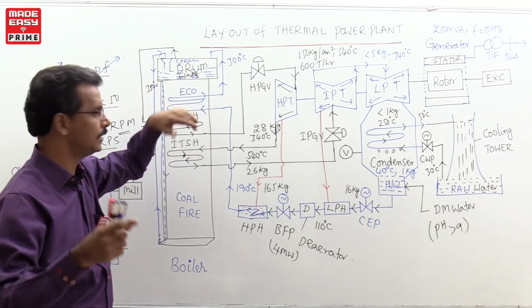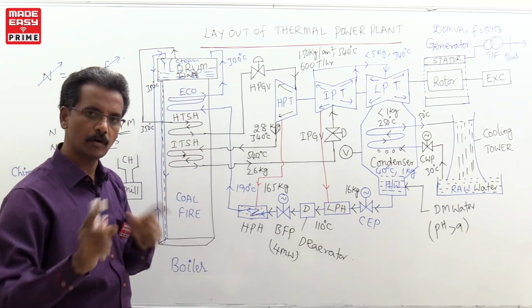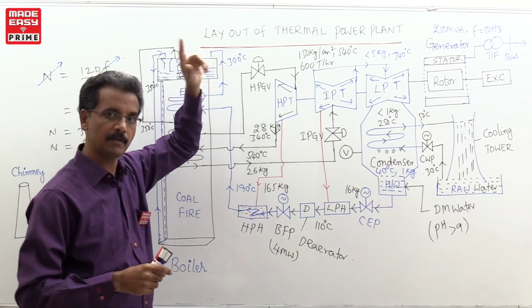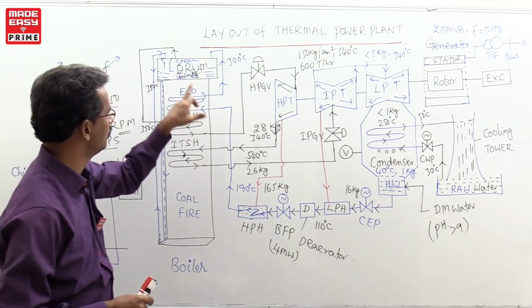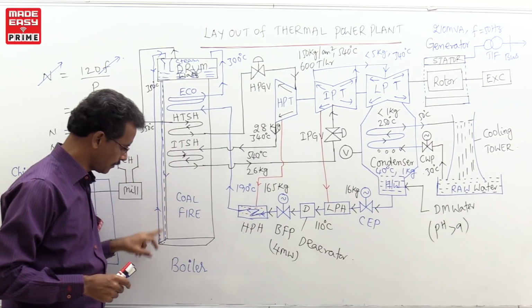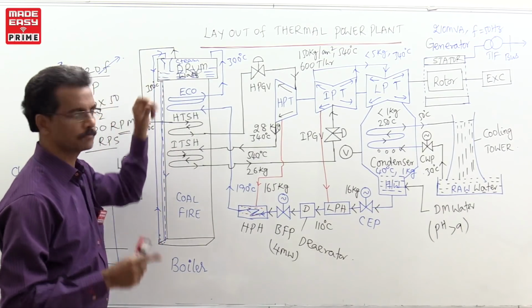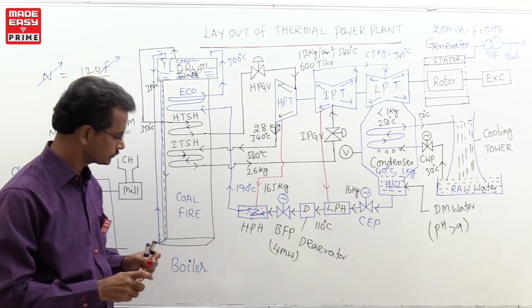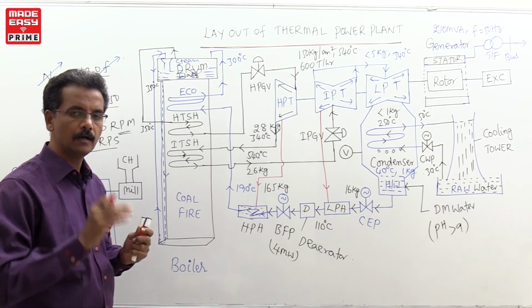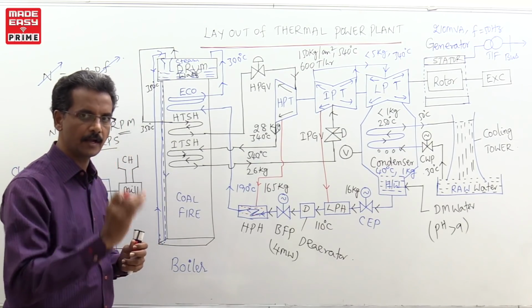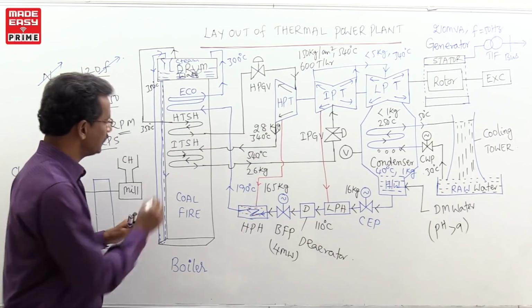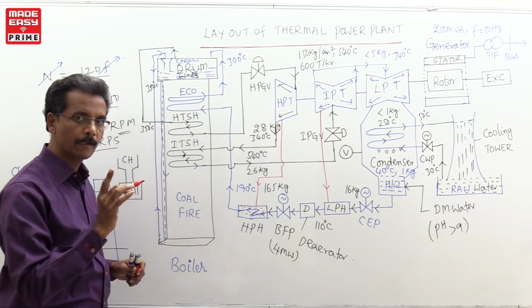In case of subcritical boilers, a drum is used. In supercritical boilers, you are not using a drum; water is directly converted to steam, as I already told. This is where the water circulates, comes back, and rises. One more important point you can observe here: in case of generators of less than 500 MVA capacity, normally they will not use any pump.